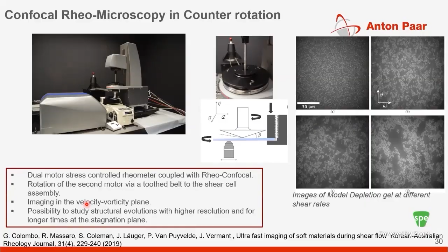So this is again an example of a multi-drive device. And here you can see that it is integrated with an additional bottom motor for counter-rotation. So this is not only rheo confocal microscopy, but rheo confocal microscopy with counter-rotation. Here the rotation of the second motor is via this belt, which is tied to the shear cell assembly. So you are doing counter-rotation, and Jan Vermant's group developed this, and they have studied many different things. This data is on a model depletion gel at different shear rates, and you get much better resolution, both temporally and spatially, which allows you to study fast dynamics under shear flow conditions. So this is another example where you can use a multi-drive device.